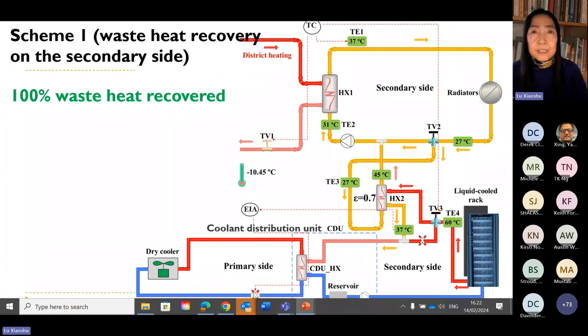And this is our invention scheme one that recovers waste heat on the secondary side. It can achieve 100% waste heat recovery. The lower section represents the direct-to-chip cooling system, and the upper section represents building space heating. The middle square represents our proposed heat exchanger that recovers waste heat from the secondary side of the CDU to supply the space heating at the temperature TE1 according to the regulated control curve that I showed in the previous slide, which is based on the Finnish regulation.